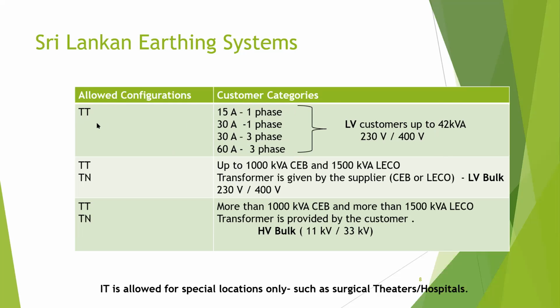These are just for your knowledge, and you should know this because when you are going to wire a house, you should design your earthing system according to TT rules. And if you are an LV bulk customer, LV bulk customer means your demand is higher than 42 kVA. If you are a CEB customer, the range is 42 kVA to 1000 kVA. If you are a LECO customer, the range is 42 to 1500 kVA.